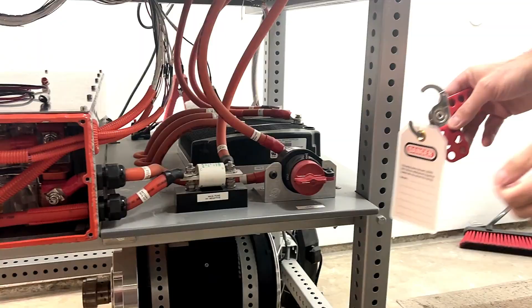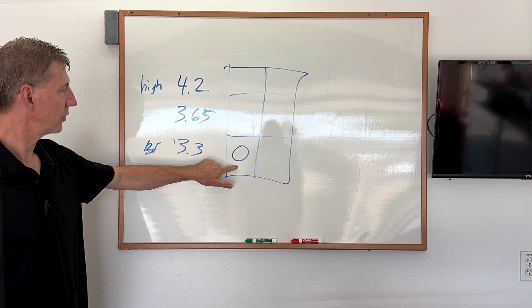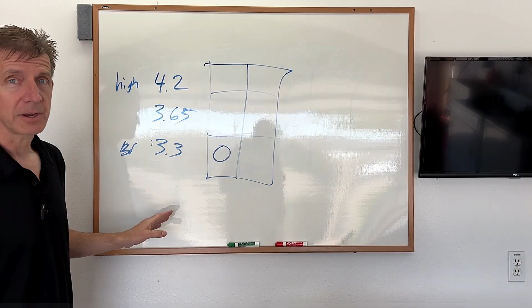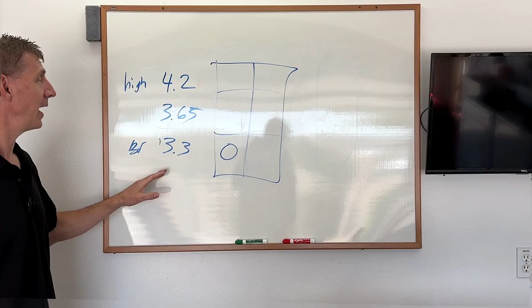For your Tesla module, cells are in groups of 6 per module. For each individual cell group, our magic numbers are: top voltage 4.2 volts, nominal voltage 3.65, and bottom voltage 3.3. Whenever any one cell group goes below 3.3 volts, we're at risk that this module is never coming back. What I've found is a pretty high percentage of the time, they actually do come back.